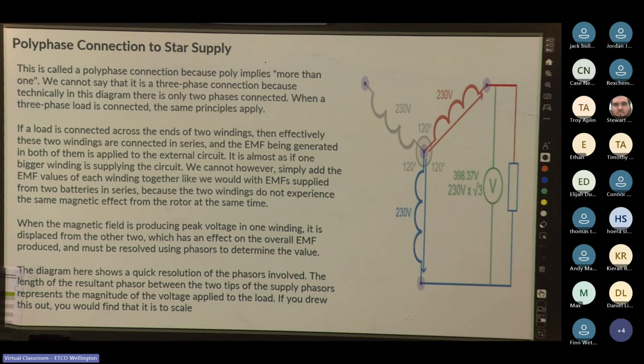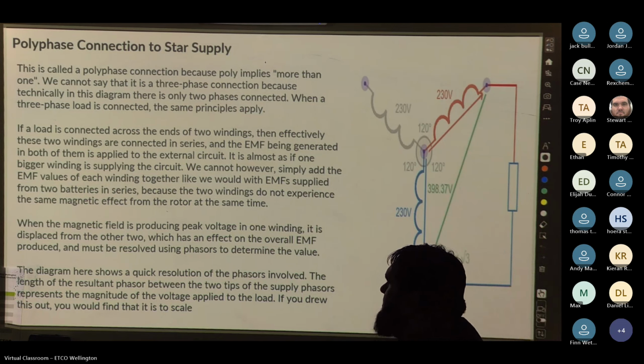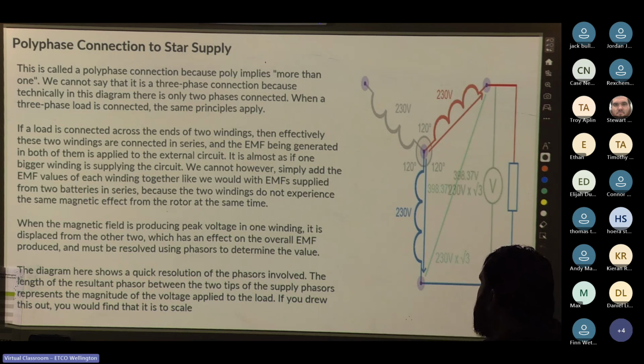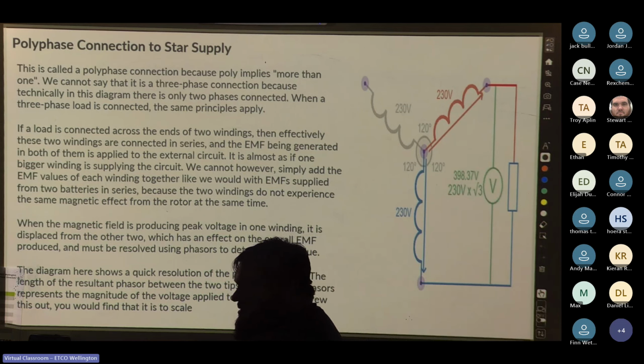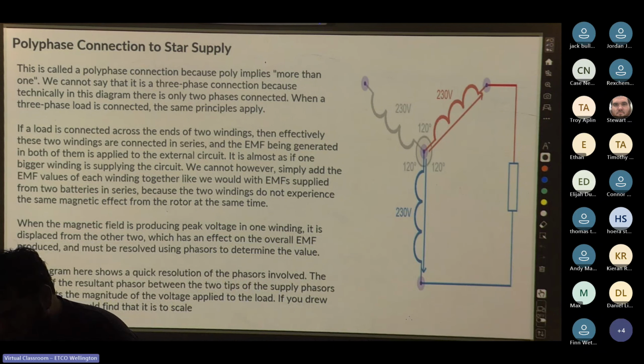So we could work this out using maths, by using Pythagorean theorem and angles, or we can use the square root of 3. So this is a relationship. If we multiply 230 by the square root of 3, we get about 398 volts. But if we were to take 400 volts and divide it by the square root of 3, we would get about 229 volts. Thereabouts 230. So whenever we're dealing with three-phase and star, the voltage relationship is dependent on this.